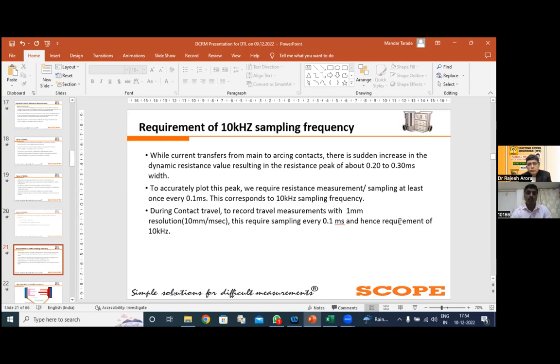Apart from that, whenever contact travel is there, to record the travel measurement with a resolution of 1 mm, we require a sampling speed equal to 10 kc. So it is very important to keep the sampling speed equal to 10 kc and the delay TCO, at the time of performing the DCRM operation, must be equal to 300 milliseconds.